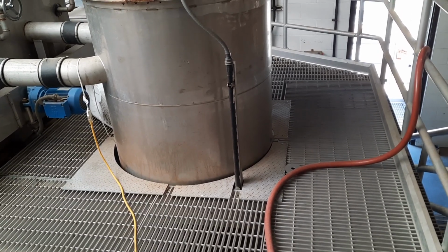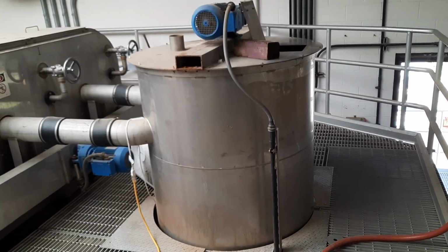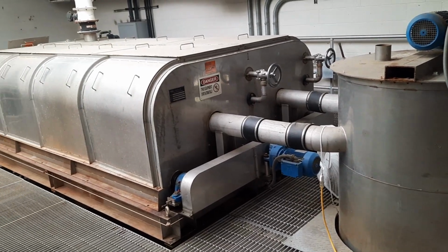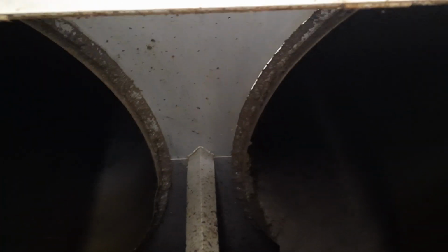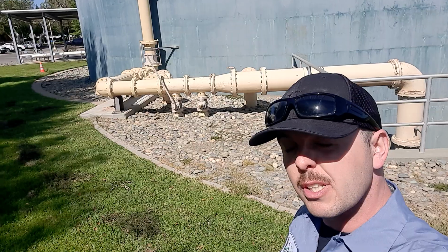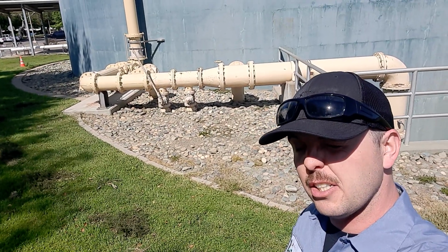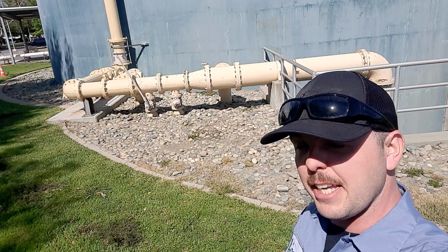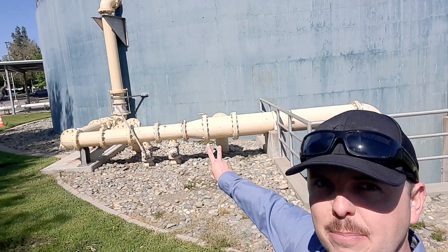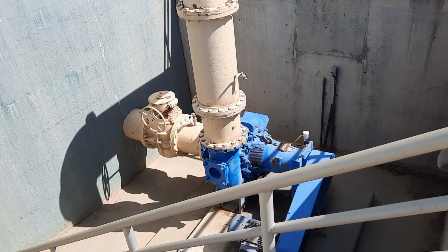The sludge being wasted out of the system is pumped up into this hopper right here. A polymer solution is added to it, and it's pumped through this rotary drum thickener. The sludge is dewatered as it goes over these perforated cones, dropped into the sump right here, and from this sump, it's going to be pumped to the digester. The thickened secondary waste sludge is mixed with the primary sludge and primary scum through these 2 pipes and pumped up into one of our 2 digesters.